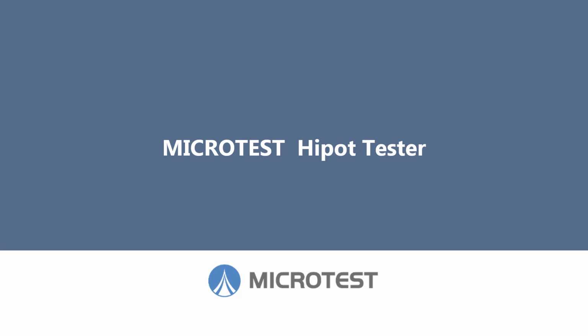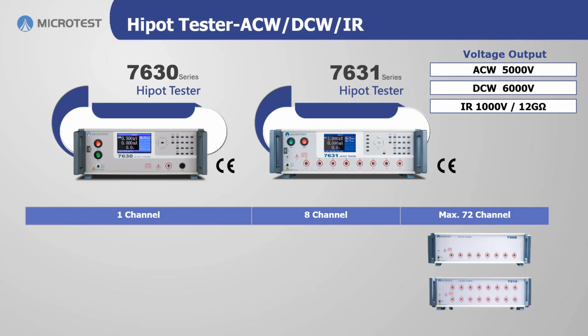Next is an introduction to the Hipot Tester. The Microtest Hipot Tester is a 3-in-1 testing instrument, providing AC, DC, and insulation resistance tests. Testing channels include single-channel, 8-channel, and multi-channel scanning boxes, supporting up to 72 test channels. In terms of voltage output capabilities, AC provides 5000 volts, DC provides 6000 volts, and insulation resistance can reach up to 12 gigaohms.